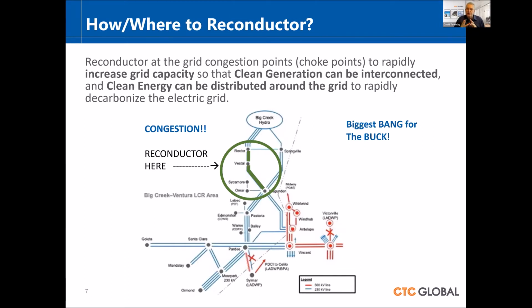So where would you reconductor using advanced conductors? We talked about all the capacity that has applied for interconnection. That means that the utility is doing studies, load flow studies, to see, okay, if you connect up over here with this much capacity and it runs this way, where are my choke points going to be? Where's the congestion going to show up? Where do I have to do something? And what we're saying is that's the very place where you want to be reconductoring. Find those congestion points. That's the biggest bang for the buck. That's where you can increase grid capacity substantially. You can then get some generation interconnected, and that interconnected generation can have its output moved and distributed around the grid, offsetting fossil fuel and rapidly decarbonizing the grid.